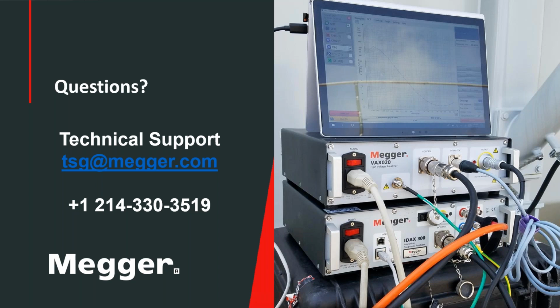Mm-hmm. All right, thank you. And while we have you, Dr. Robolino, can you perform hot collar tests with the Idax? Especially if you have the 2 kV system, why not? I mean, the same things that you can do with your power factor test set, you can do with Idax. Idax, again, is a different approach talking into the dielectric frequency response analysis, but you can do your power factor test like we were showing before.